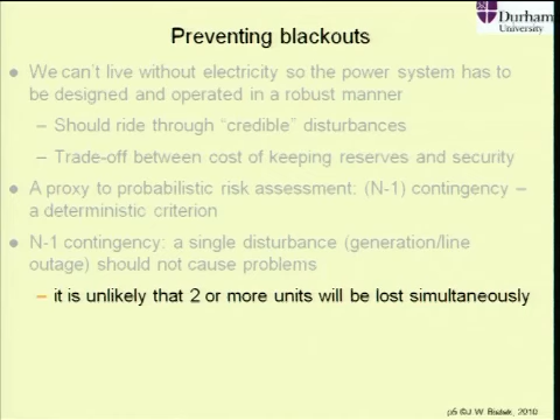We assume it's highly unlikely that two or more units will be lost simultaneously. That means we should carry power operating reserve, generation reserve, such that the loss of the single largest infeed, meaning generation, should be covered by other units connected in the system. In this country, the largest unit is a nuclear reactor at Sizewell B, at 1320 megawatts. So at any time, if we lose Sizewell B, everything will be fine, because there's enough generation connected to the system to carry that reserve.